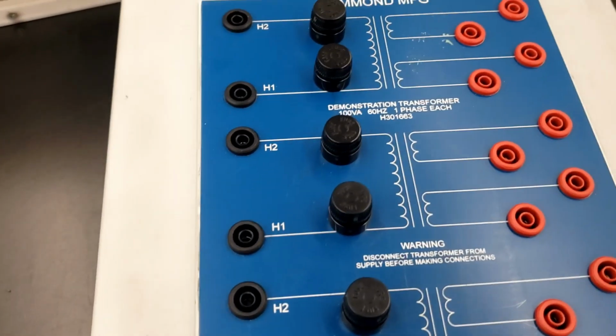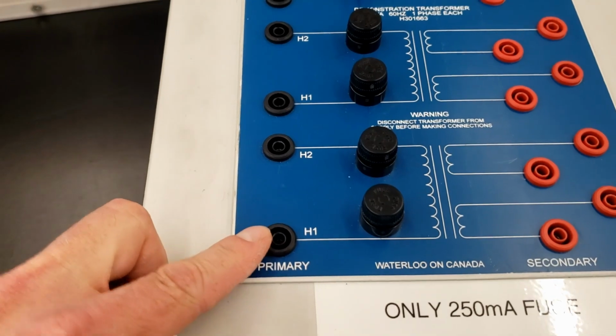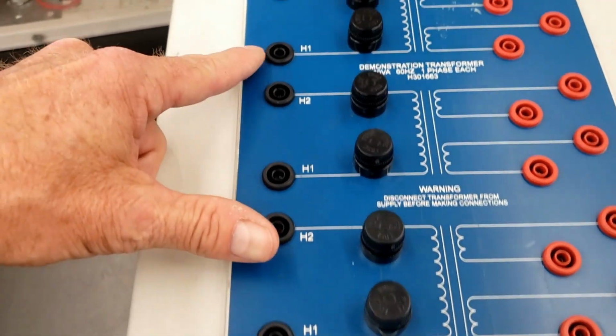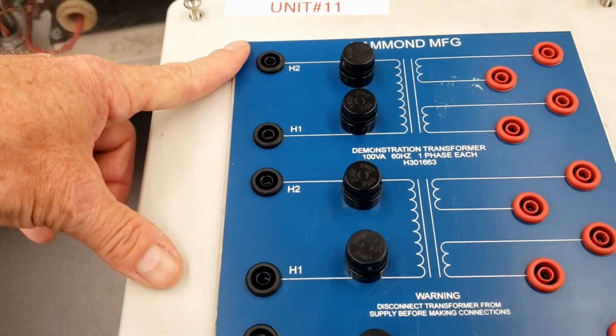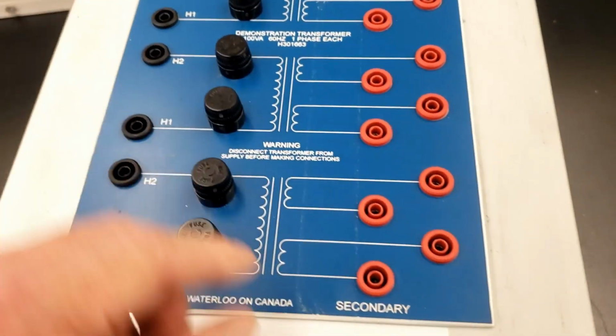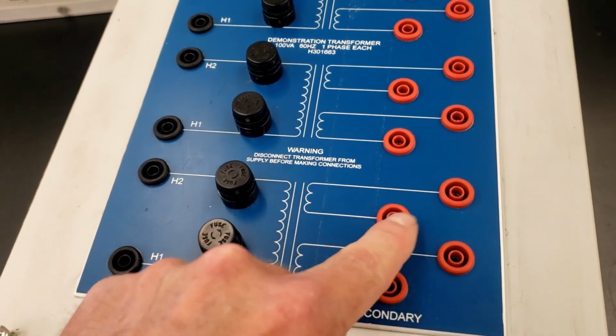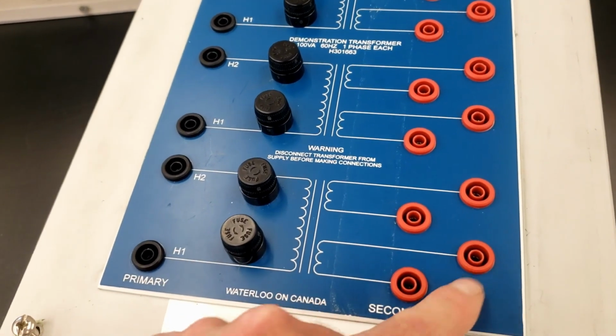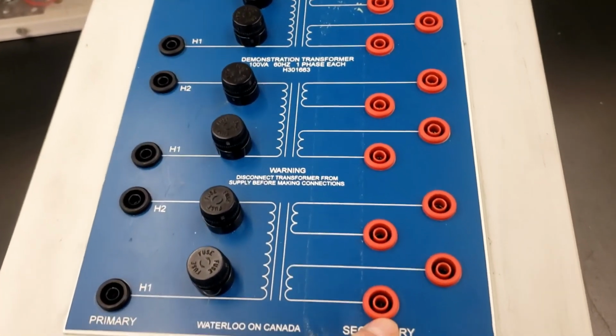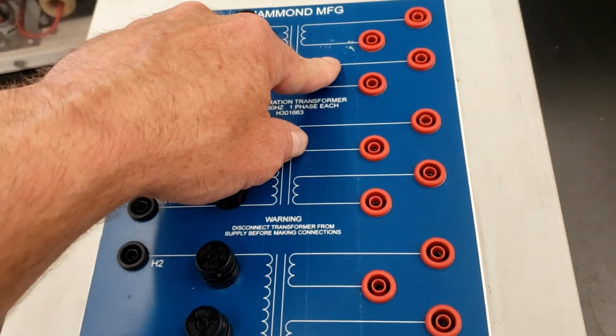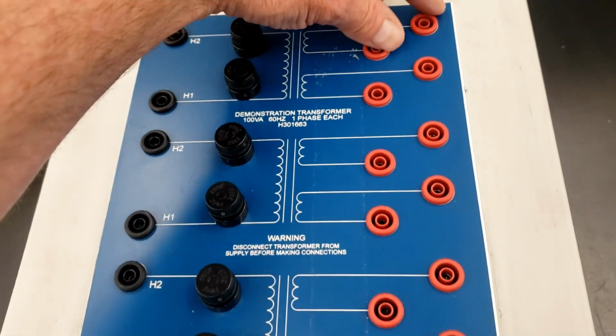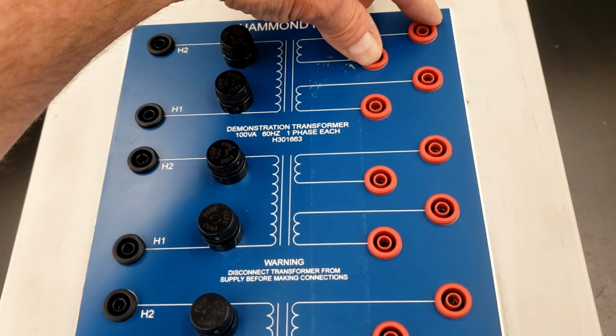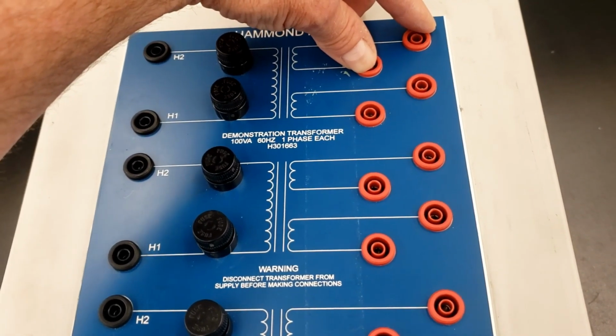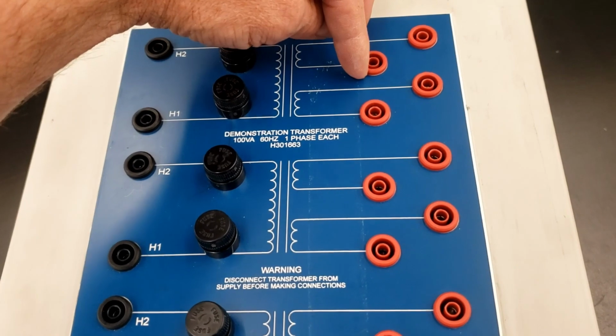They are randomized so they won't exactly be like these. The H leads are clearly marked H1, H2, H1, H2. Primaries are all the same polarity, but the secondaries may be labeled differently, like X1, X2, X4, X3. They may be randomized between transformers, and they're definitely specific windings, like X1 and X2, or X3 and X4. We're just not sure which is which because they've been randomized.